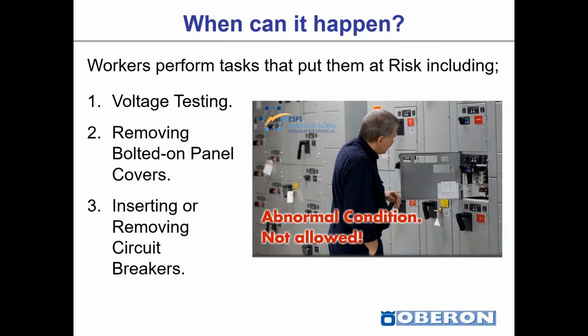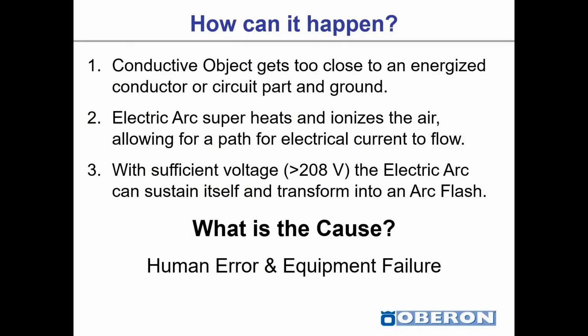When can it happen? Workers perform tasks that put them at risk, including voltage testing, removing bolted on panel covers, inserting and removing circuit breakers, just as a few examples. How can it happen? A conductive object gets too close to an energized conductor or circuit part and ground. An electric arc superheats and ionizes the air, allowing for a path for the electrical current to flow. It does require sufficient voltage. The electrical current can sustain itself and then transform into an arc flash.